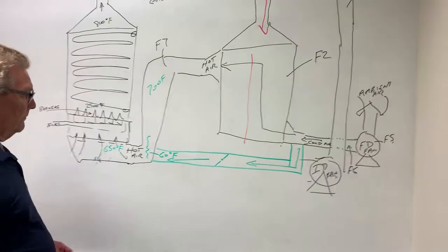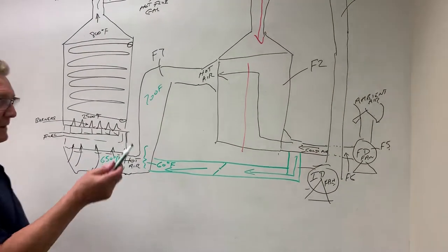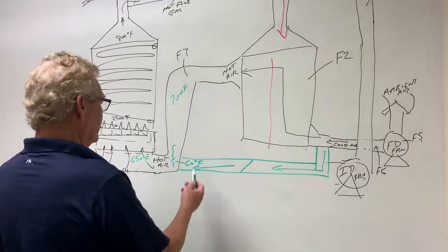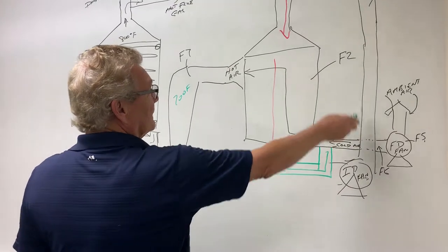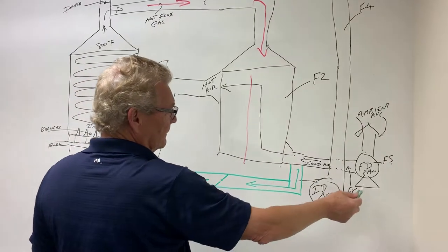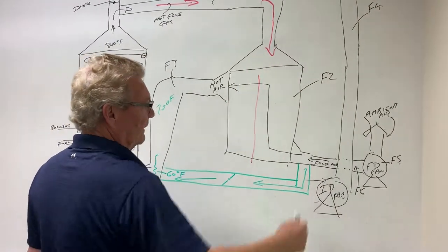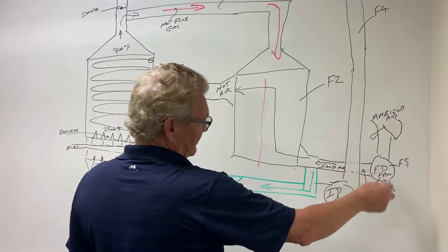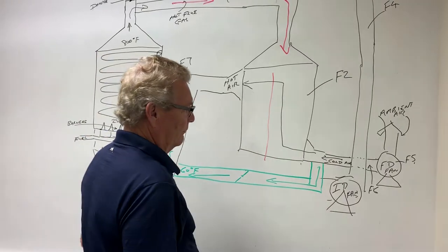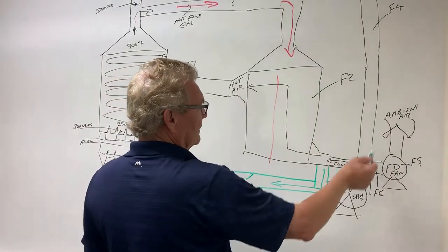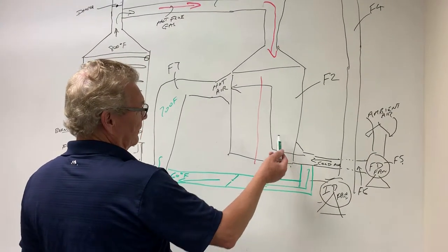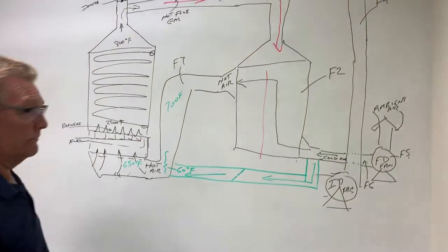And what are the benefits of having cold air bypass? This is covered in the script, but basically the benefit is that we maintain the flue gas outlet temperature. As the ambient air drops below 60 degrees, the temperature going to the stack would keep dropping. Particularly if we get down below freezing, we can start to get corrosion taking place in the air preheater. So this helps maintain the flue gas exit temperature. Although the cold air is still going to be cold air going into the exchanger. Okay.